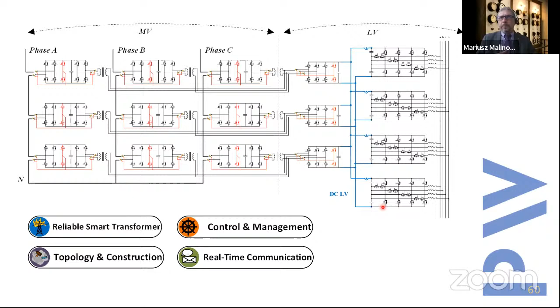protocol for communication. And when we look at the final topology, we see plenty of converters together. To control all of them at the same time, you see how difficult it is, because we can count here plenty of local controllers, including the DSP, as well as some master controllers: one master controller for the top control layer, a master controller from medium voltage AC to low voltage DC, and a separate low voltage DC to AC controller.